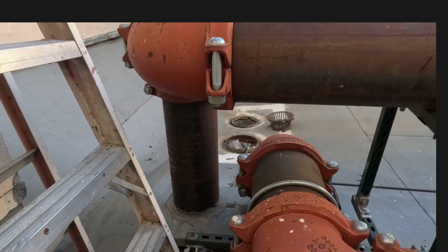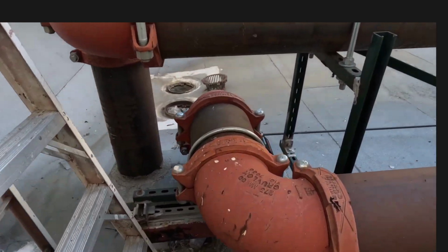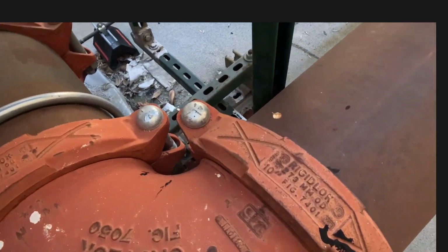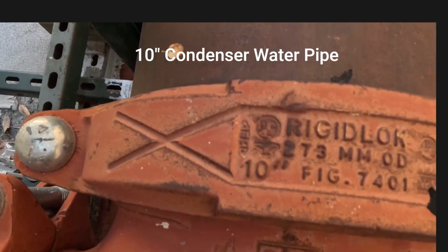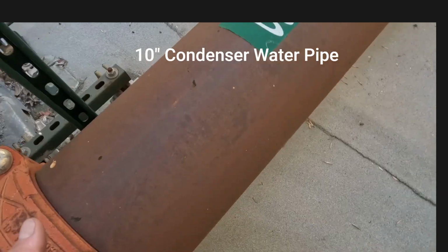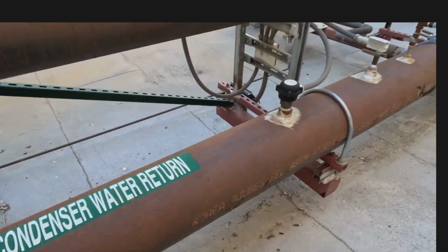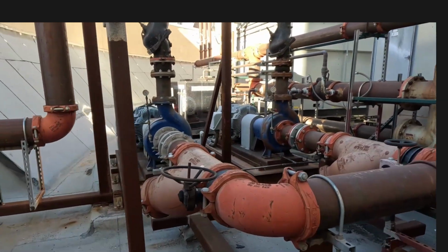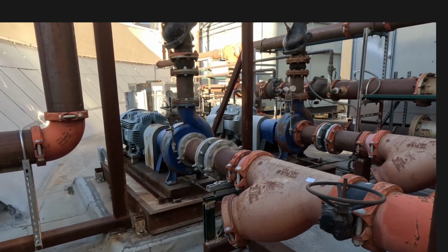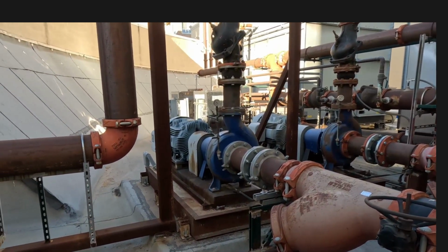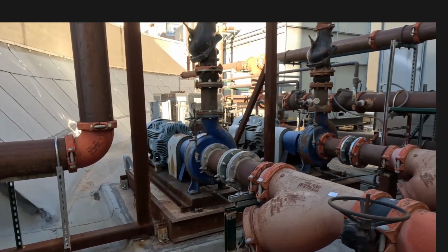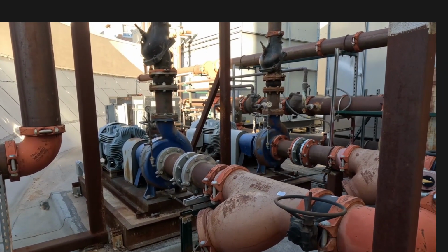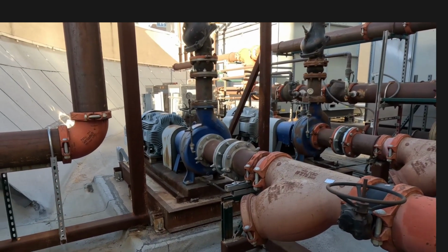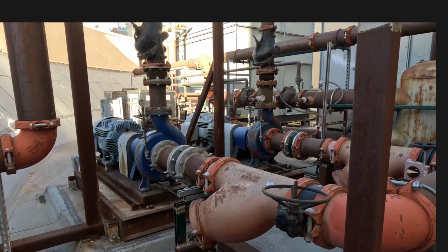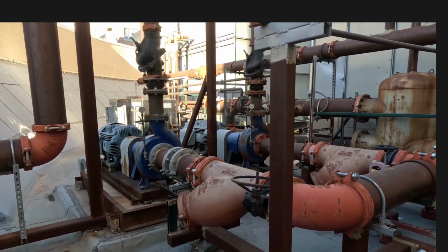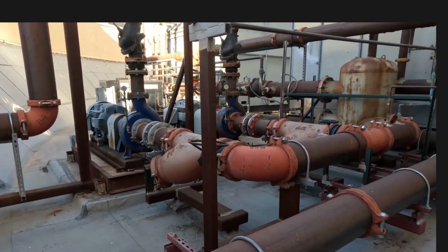So you can see how big this pipe is, right? Coming in the building. This pipe right here, you can see on the couplings here, 10-inch. That's the size of this coupling, so I can tell that this is 10-inch pipe going right here. You can see we got the pumps right here. These are massive pumps that pump water throughout this whole building. And only one of them's operating right now, which is this one right here. The other one's kind of off. They don't really need two pumps operating at the same time. One of them's capable of maintaining the load, but they have a second one for redundancy. And so throughout the day, they switch back and forth so they can have an even run time.